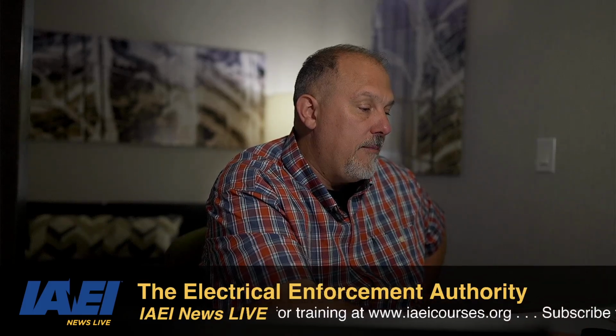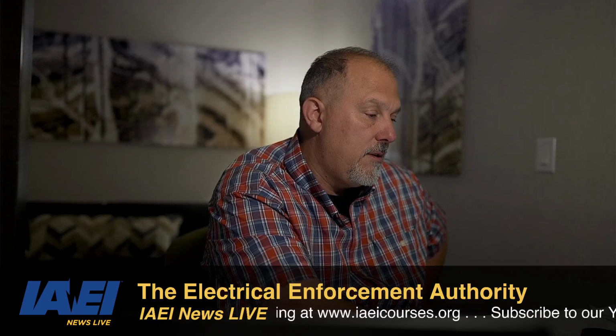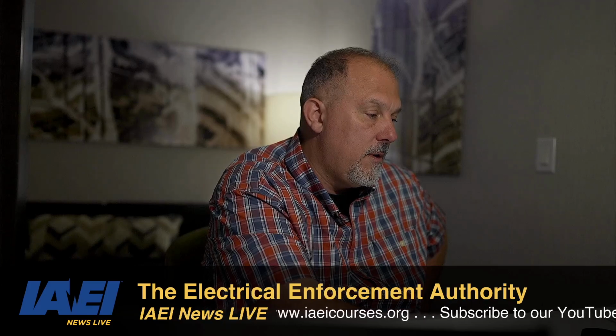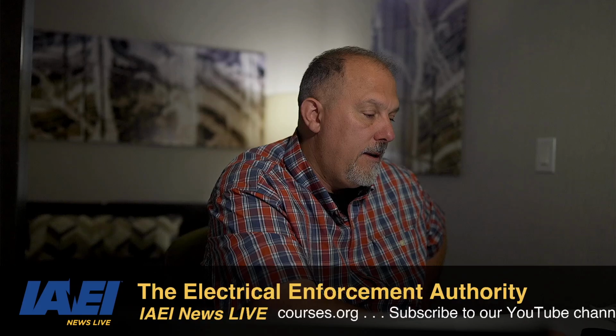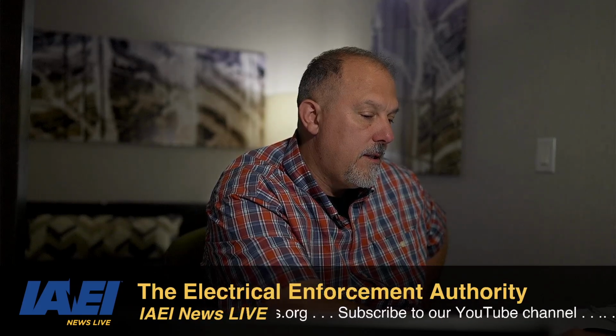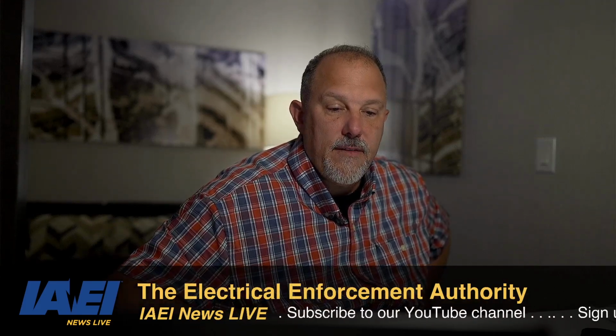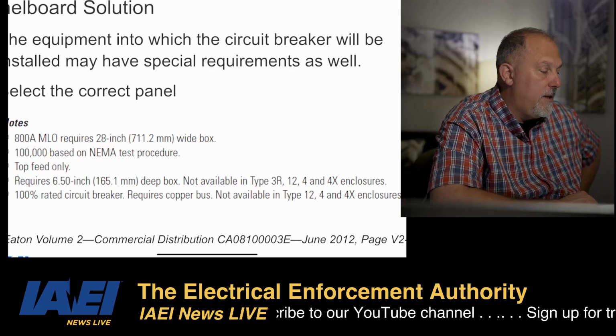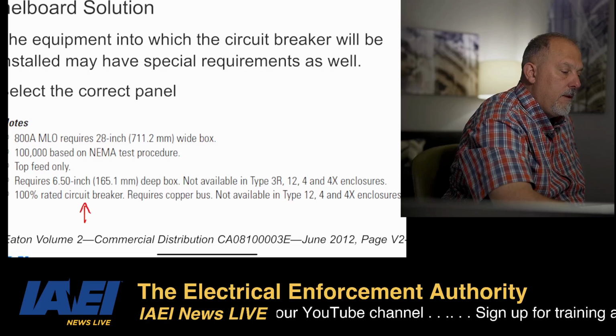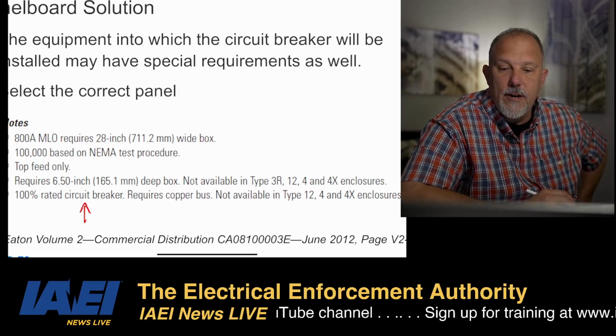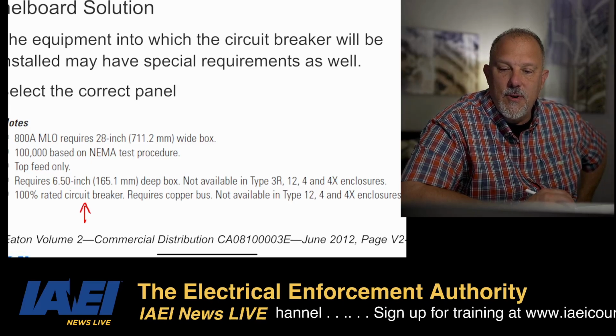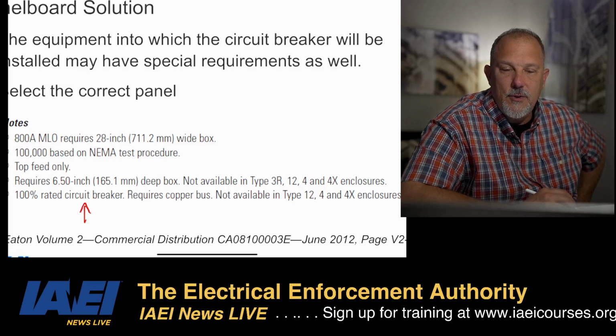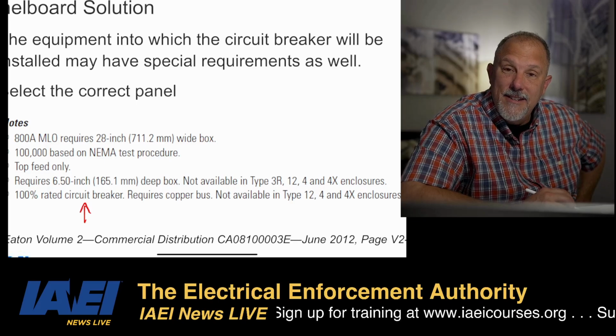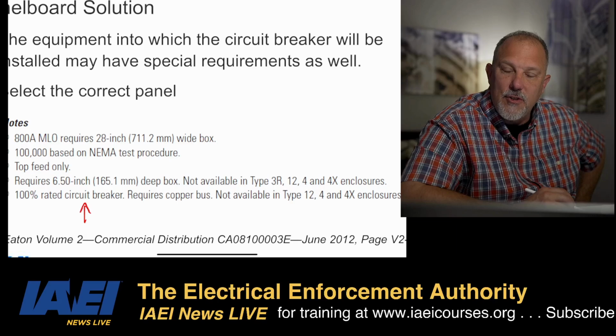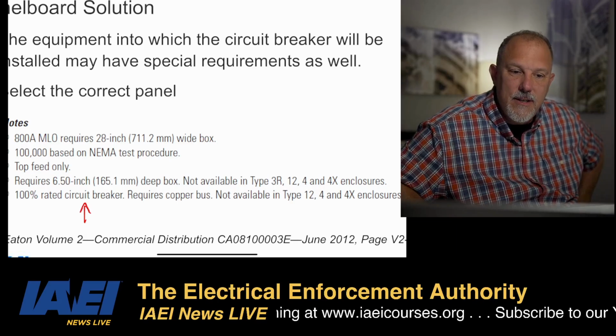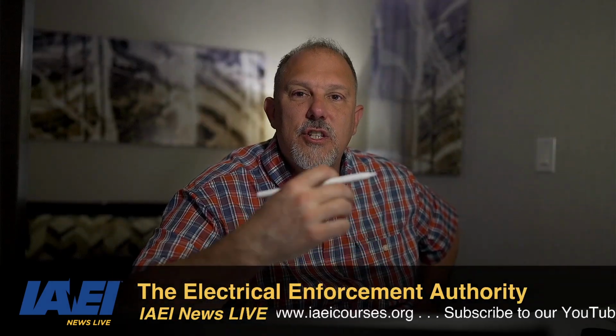And you'll see in manufacturer's instructions, look at this. This is out of a manufacturer's instructions literature. Look at this right here. 100% rated circuit breaker requires copper bus. Not available in type 12, 4, and 4X enclosures. So you're not going to see an aluminum bus in a panelboard or switchboard or whatever it is you're using with 100% rated devices. It tells you it's more than just the circuit breaker.